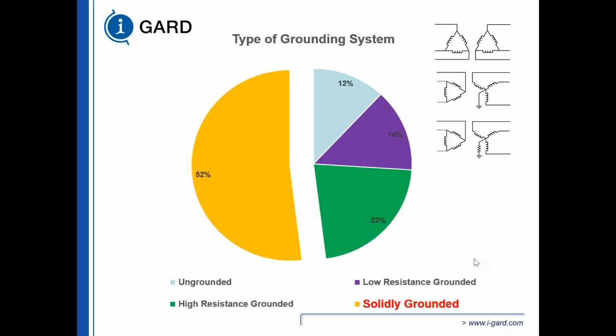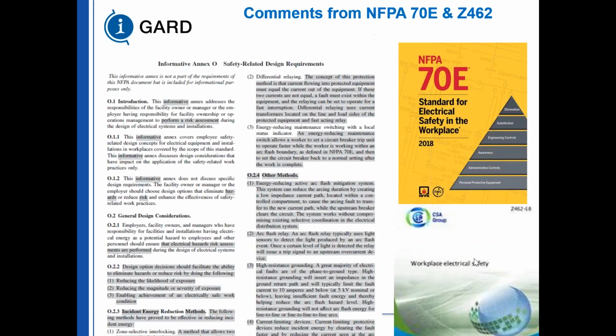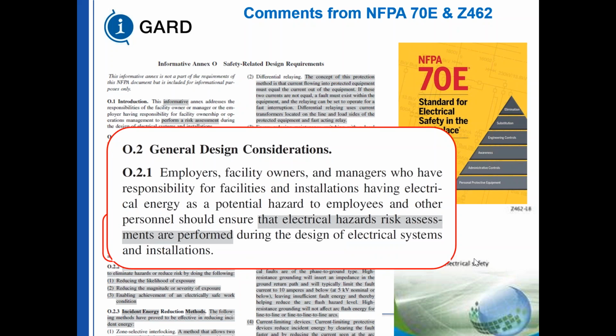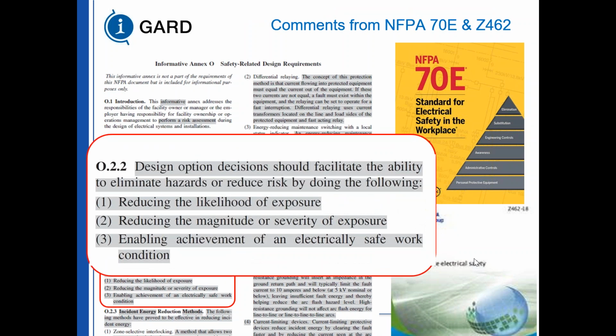So the next one we're going to discuss is solidly grounded systems. In solidly grounded systems, 52% of the installations, industrial or commercial, are going to be solidly grounded. And it may be for the wrong reasons, but they are solidly grounded. Employers, facility owners, and managers who have responsibility for facilities and installations having electrical energy, and you guys all know this, is 70E and Z462. Electrical hazard risk assessments are performed during the design of electrical system installations. One thing we have to do is reduce the likelihood of exposure and reduce the magnitude or severity of exposure.